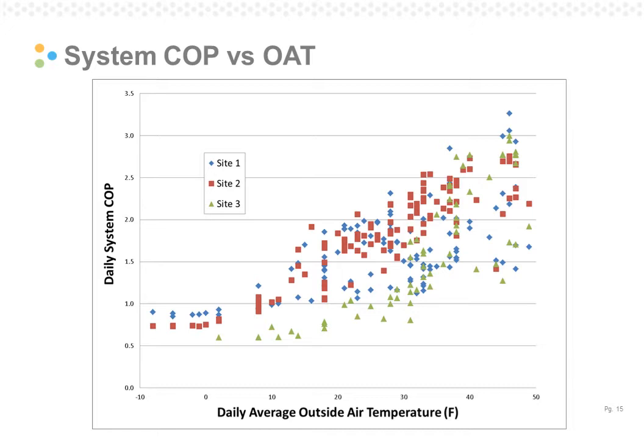On this slide, you can see the system coefficient of performance versus the outdoor air temperature, and these are daily averages. On the y-axis, we have the daily system COP. So by system, I'm talking about the air source heat pump with the propane furnace as a backup. And these events are heating events only. This chart does not include any cooling data. And then on the x-axis is the daily average outdoor air temperature in Fahrenheit.